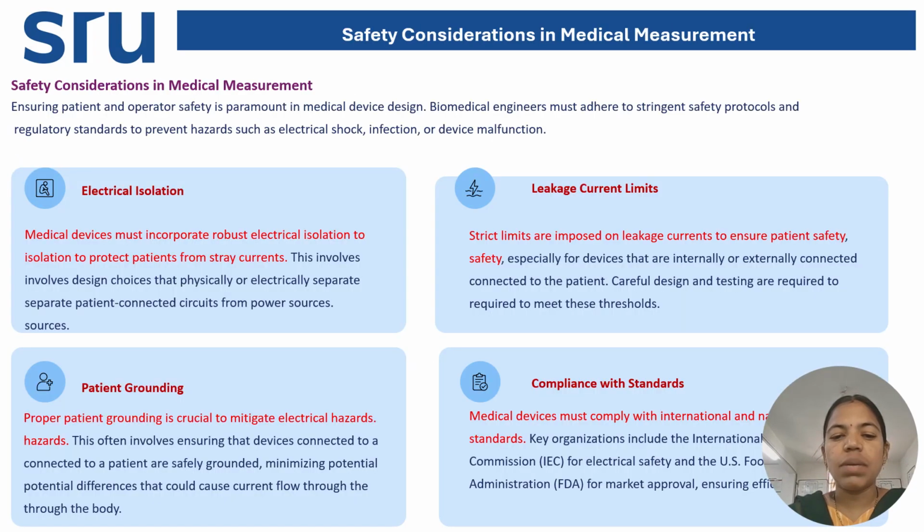Now, safety. The electrical isolation must be maintained. Medical devices must incorporate robust electrical isolation to protect the patient from stray currents, or leakage currents. Strict limits must be imposed on the allowable leakage current so that the patient will be safe and there will not be any risk.